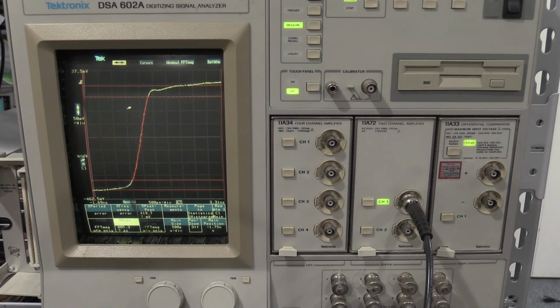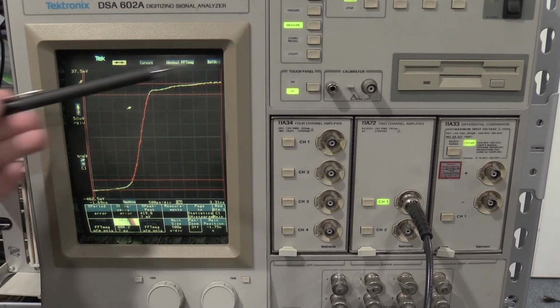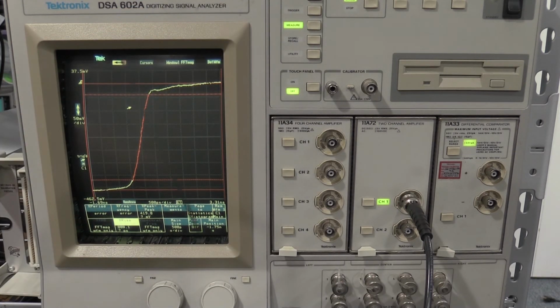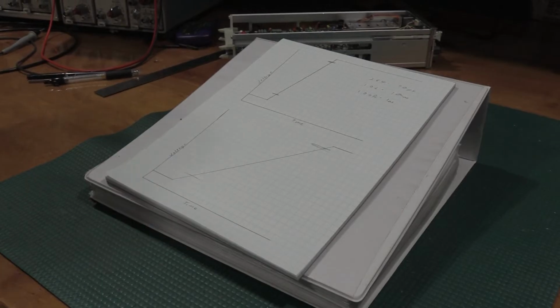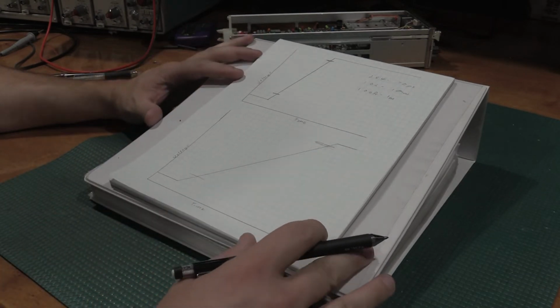This is also why I have to use several different calibrators when I'm doing an oscilloscope, because this gets me a decently fast edge, but then I have to use the tunnel diode pulser. Problem with the tunnel diode pulser is it doesn't stay flat after 20 nanoseconds. It climbs up till the waveform brings it back down. So I get a fast pulse and a good settle, but I don't get a decent long-term stability on the square wave.